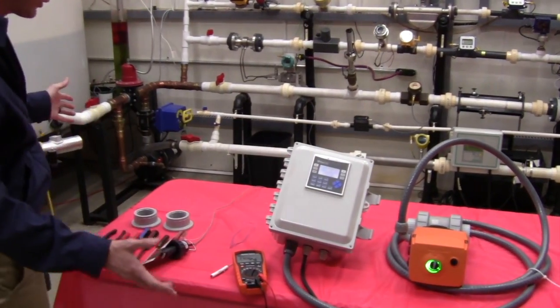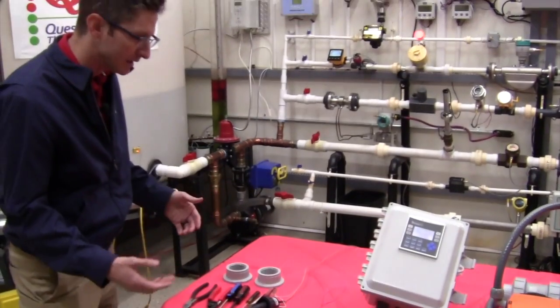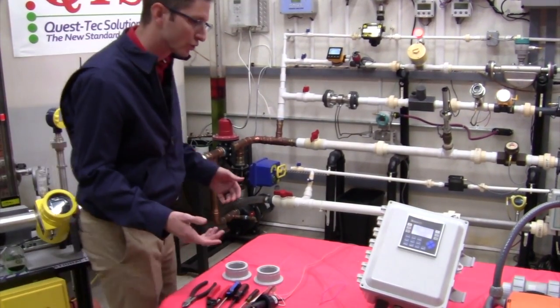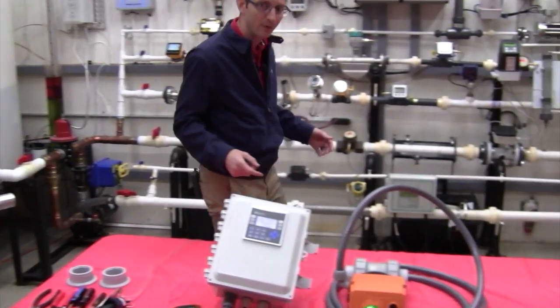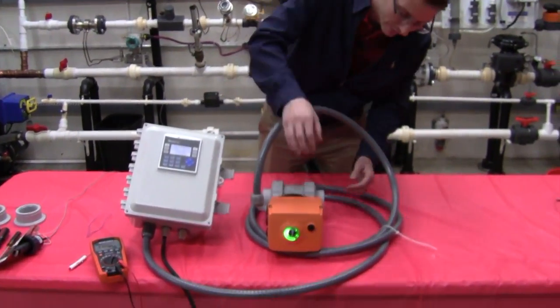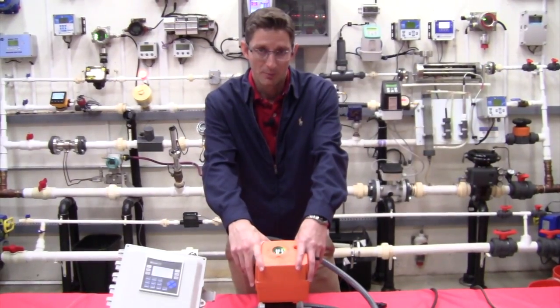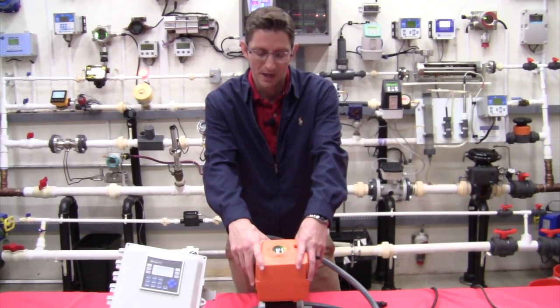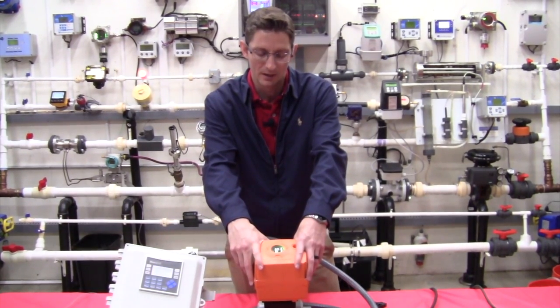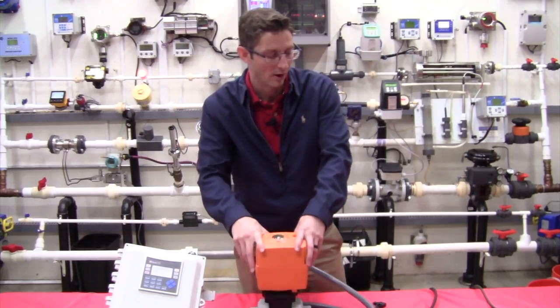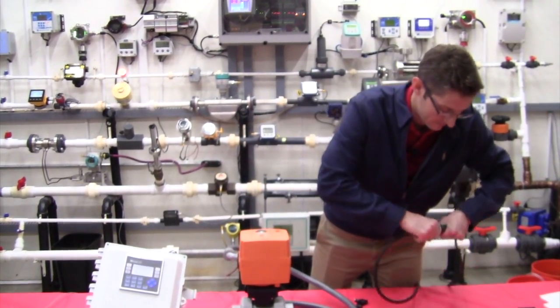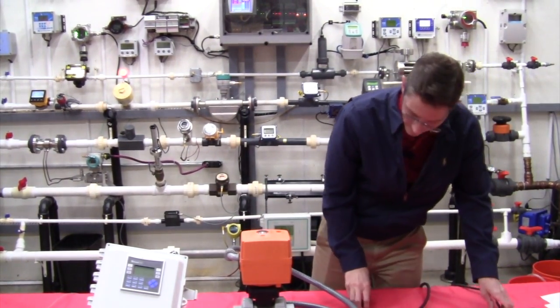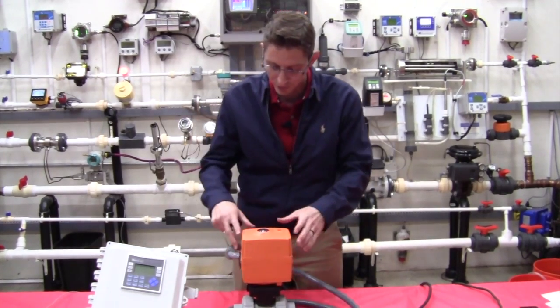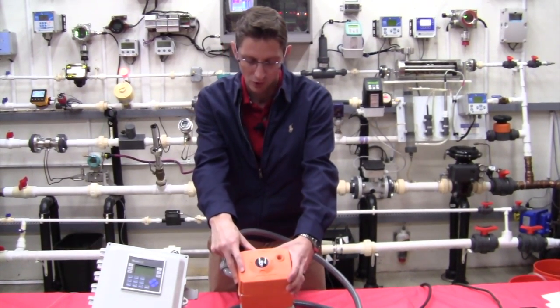The only other thing you could ever need to test or troubleshoot would be the valve itself. So if we come over here to the valve, I'm going to unplug the valve now and show you how to manually operate the valve when you take power off. All right, so now power is killed to the unit. The valve is in the closed position.